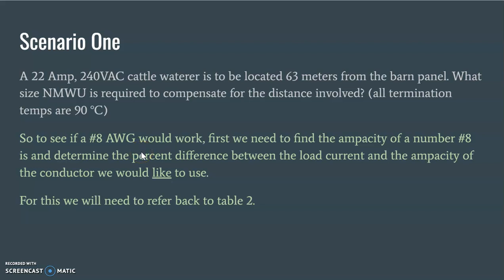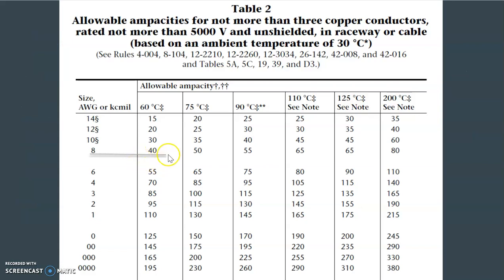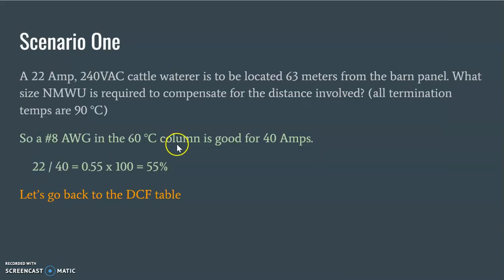So first thing we got to do is if we're trying to go to a number 8, we have to figure out what the ampacity of that number 8 is, and then figure out what the percent difference is between the load that we're going to place upon it and what the ampacity of the cable is that we would like to use. So we have to go to Table 2 for that. So let's take a look at Table 2. And again, remembering that it's NMWU and it's only good for 60 degrees Celsius, we have to go down this column here, and a number 8 is good for 40 amps. So now that we know that and we know what our load is, because we've got that in our scenario here, 22 amps divided by 40 is 0.55, times that by 100, and it gives us a 55 percent loading of our cable.